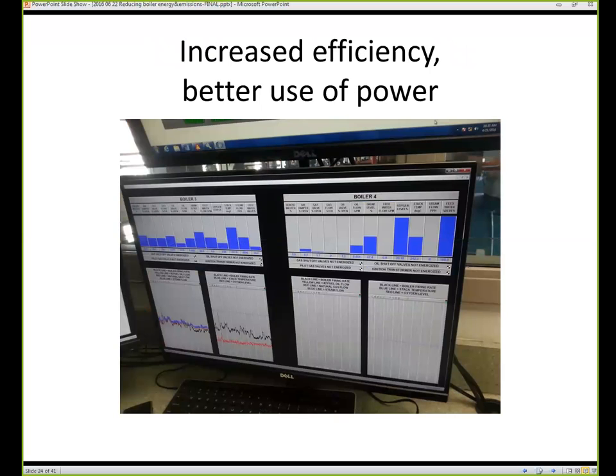Okay, increased efficiency, better use of power. What we have is at our plant, we set all our own combustion. Now, I know a lot of you with liability or whatever have a company come in and do it. Typically, we'll run our boilers anywhere from 3.5 to about 5 on O2. CO as low as we can get it, usually 0 to 10. If we're getting one that's been a little finicky, I might run it at 50 ppm, but very seldom do we do that. Sulfur dioxide, 0. Nitrous oxide, we're right around 100 most of the time, and this is on natural gas.